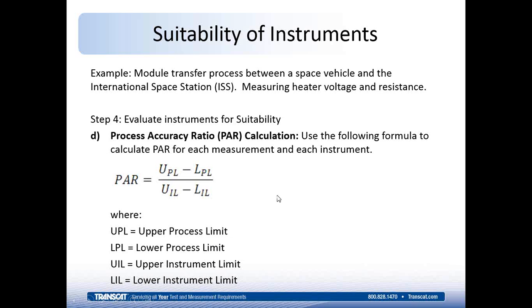All right, so the next thing to do is, and this may be a new term to some of you, this is a Transcat term that we've come up with to reference another term that has been used in the metrology world anyway. And that term is the test accuracy ratio, which we've converted now to a process accuracy ratio, to focus on that measurement that's used in a production or testing process. All right, so the process accuracy ratio is a calculation that takes the upper limit of the process minus the lower limit of the process, and I'll show you where those come from, and divides that by the upper limit of the instrument minus the lower limit of the instrument.